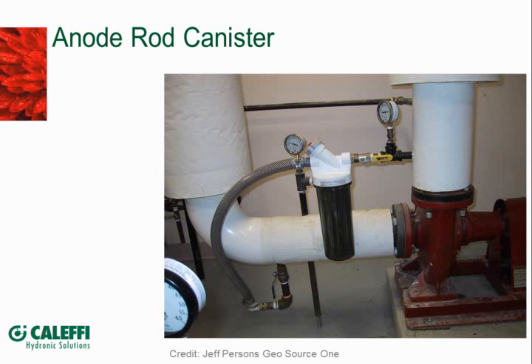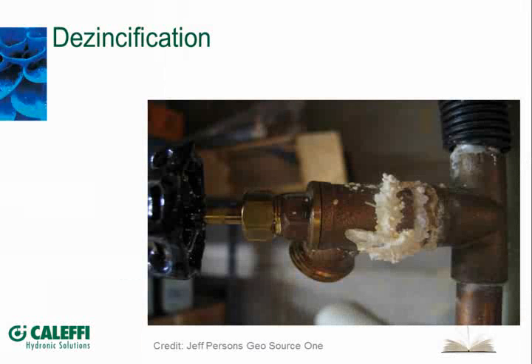Here's a commercial geothermal system running at temperatures between 40 and 70 degrees Fahrenheit. This building was piped all in black iron pipe, circulating around to 22 horizontal geothermal machines above the ceiling. Within about five years of construction, it began experiencing leaks at brass-to-threaded black iron connections. It was all attributed to a combination of galvanic corrosion and methanol in the system. We abated that using sacrificial anode rods in a canister with a simple bypass at one of the two primary pumps for the system. It worked quite nicely.